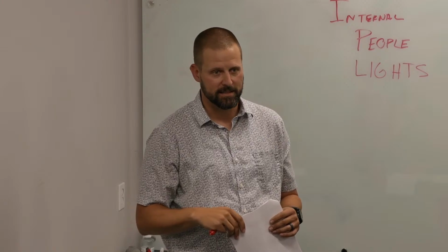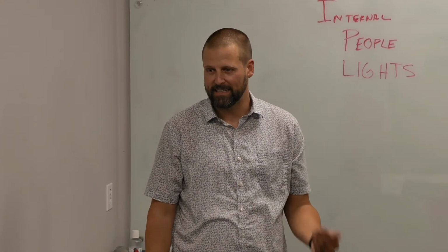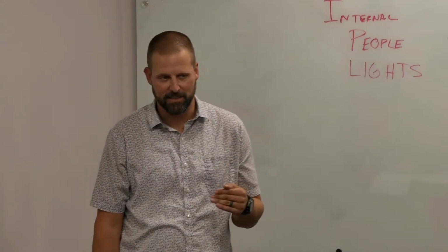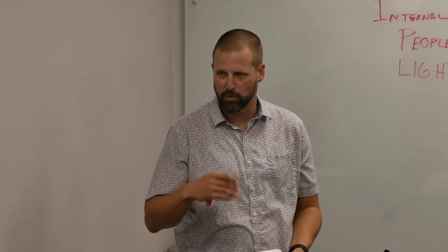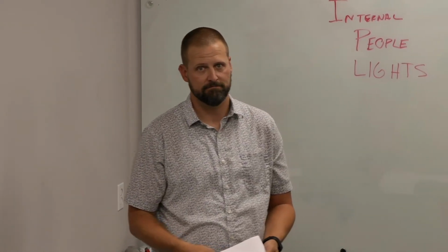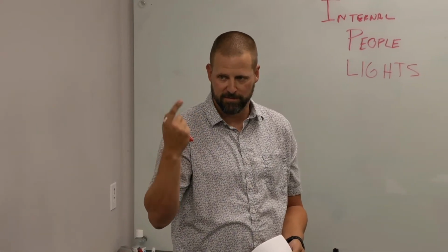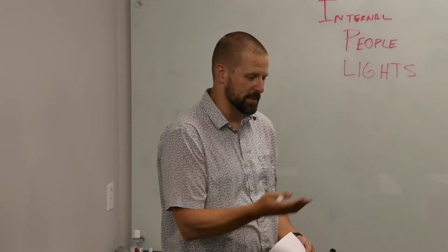The thought being it could change, and lights are generally not a huge part of the load. So a very typical normal office building would be like 1 watt a square foot. That has changed a lot in the last 20 and even more in the last 40 years, because LED lights use far less energy than fluorescent or incandescent.